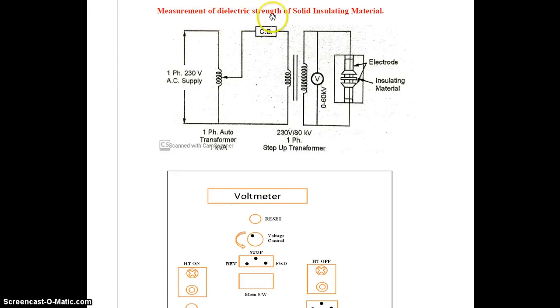Measurement of dielectric strength of solid insulating material, in which the construction diagram is shown in the figure. On the input side, we apply a single phase 230 volt AC supply. This supply is given to the single phase auto transformer. The rating of the transformer is 1 kVA.